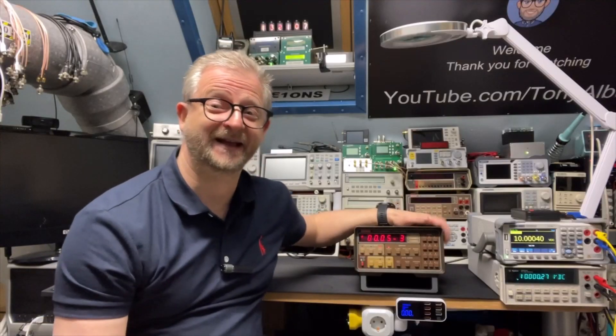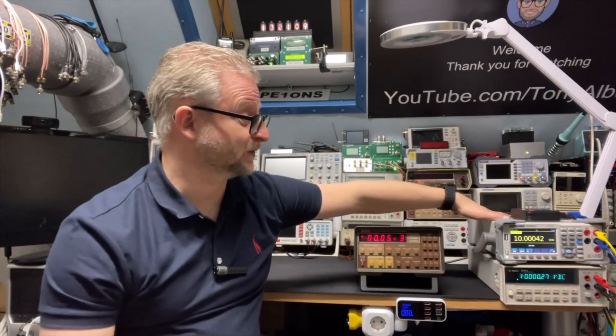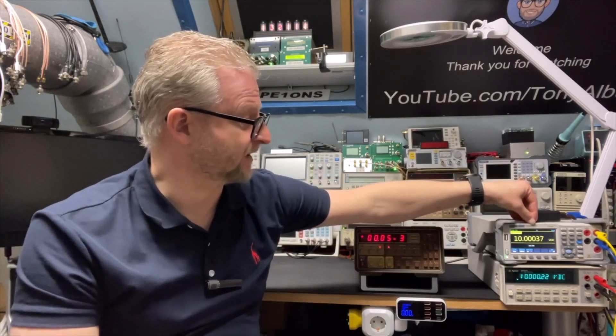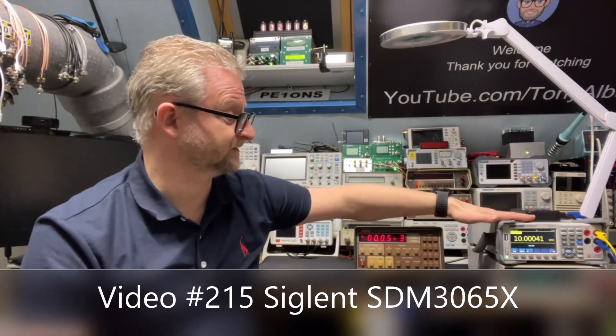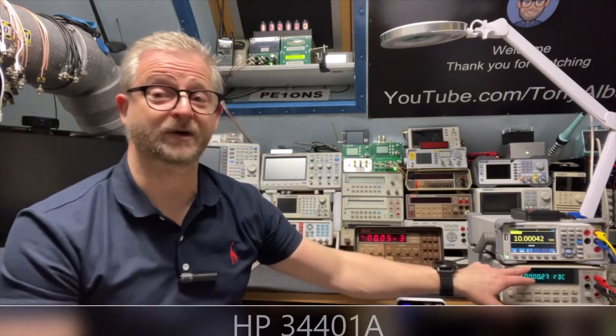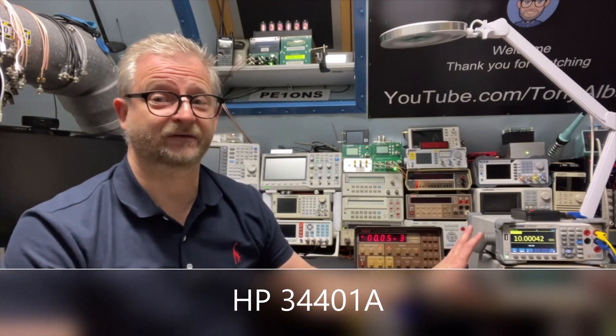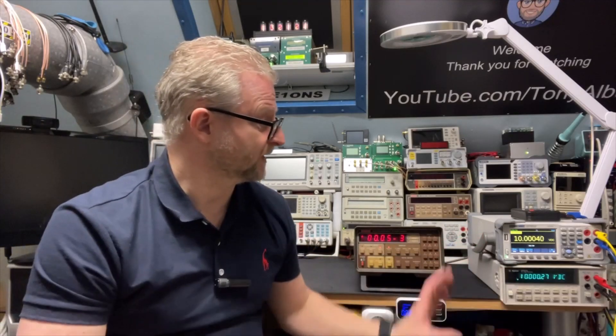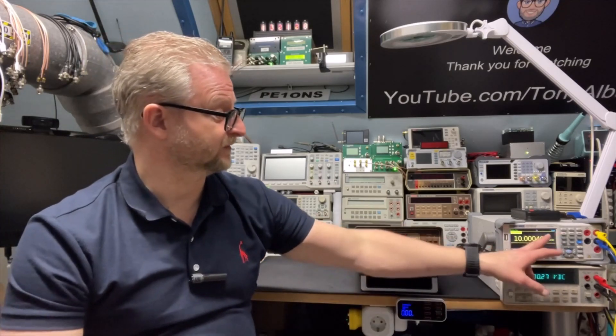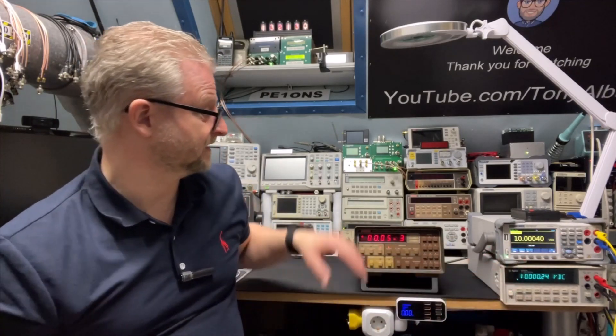So on the bench, I have already my multimeters here heating up. It is the Siglent 3065, it is 6.5 digits. I also have the HP 34401A. They are both heating now for an hour. I will wait another hour and as you can see, they almost agree up to a few microvolts. So that is okay.